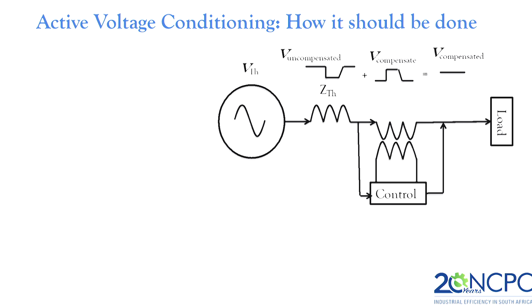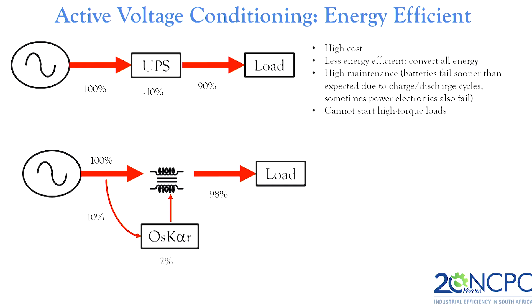So there's a UPS example, let me be quick. We'll lose 10% of the energy coming off the grid to supply you with about 90% continuously. This is about the losses expected when you convert all the energy through power electronics. But this device achieves energy efficiency in real life nearer to 99%, though I've written 98% here, by only taking the part of the energy that's not correct and instantaneously fixing the voltage signal, and it costs much less.